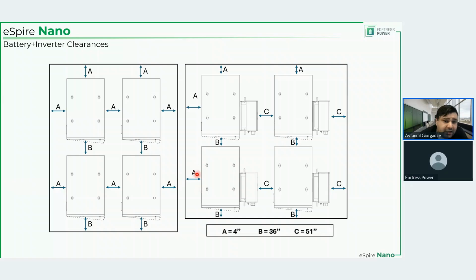And number 4, or I'm sorry, A is 4 inches. A is the clearance behind the inverters. B is 36 inches because this door needs to be open somehow, and also HVAC is here, so it needs ventilation. But on the sides where you don't have the door, where you don't have the inverter, 4 inches is sufficient on the battery cabinet side.